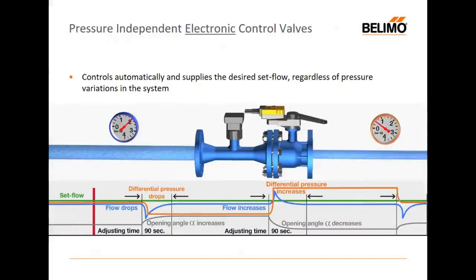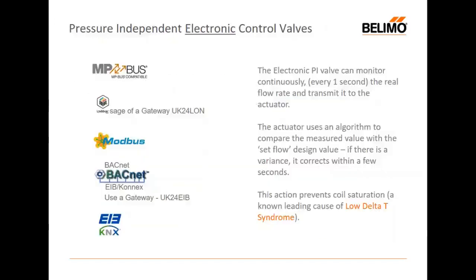And this is a short animation to show you an underflow, the valve opens, and then an increase in pressure because of interactivity, the valve starts to close. And it's as fast as that. It's catching the overflow at source. We're not waiting for a thermostat to trip. We're not saturating a coil. We're not doing anything to undermine the efficiency of the system. We're acting on real measured values. When we've got those values, we can communicate them in a number of ways.